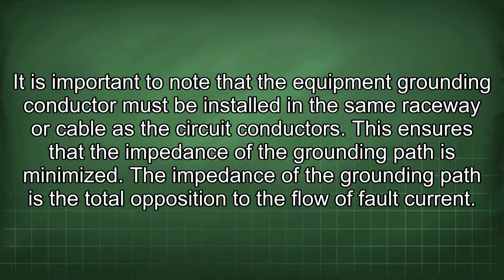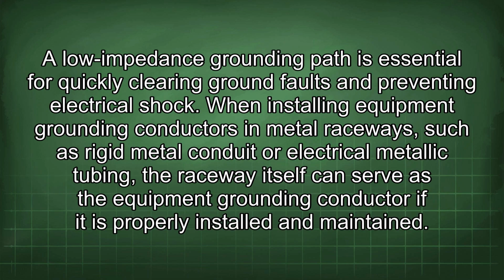It is important to note that the equipment grounding conductor must be installed in the same raceway or cable as the circuit conductors. This ensures that the impedance of the grounding path is minimized. The impedance of the grounding path is the total opposition to the flow of fault current. A low impedance grounding path is essential for quickly clearing ground faults and preventing electrical shock. When installing equipment grounding conductors in metal raceways, such as rigid metal conduit or electrical metallic tubing, the raceway itself can serve as the equipment grounding conductor if it is properly installed and maintained.